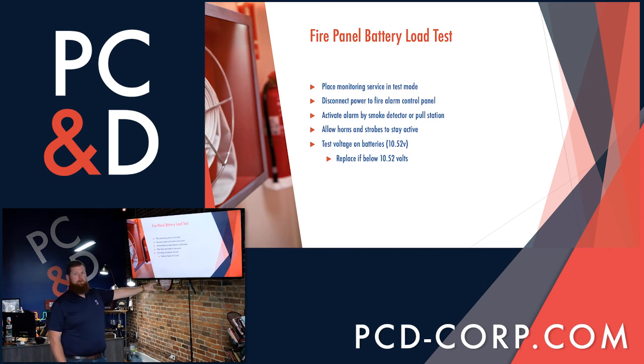Now, just to clarify, when I mean in use, it's if we were to simulate a fire drill, we would leave the horns and strobes active at all times and check only the voltage. We're not interested in amps or watts. We only want to see how many volts remain on each battery. As long as it remains above 10.52 volts, while again, the horns and strobes are active, then your battery's passed. If they did fail, then they will need to be replaced and documented.